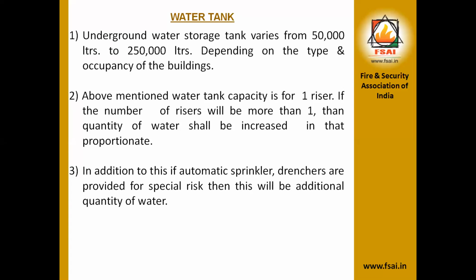as we have seen in the previous slides, the sprinklers are provided at each floor level. So if the automatic sprinkler drenchers are provided for special risk, then this will be an additional quantity of water. As the number of sprinklers increases, the quantity provided should be more, and accordingly the size of the water tank should be more. So everything should be considered in design. Next is the sprinkler.